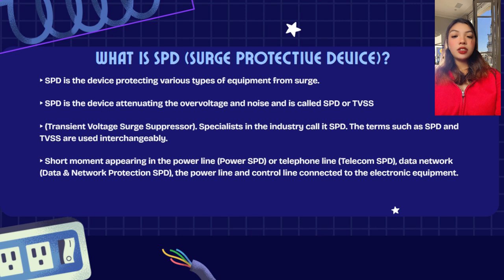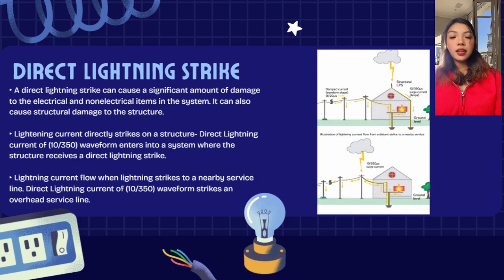The next slide is the direct lightning strike. A direct lightning strike directly hits a structure or line. It produces a very high energy surge and uses the 10/350 waveform. The effects of this are severe damage to electrical systems, electronic devices, and building structures. This is the most destructive type of surge but less frequent.